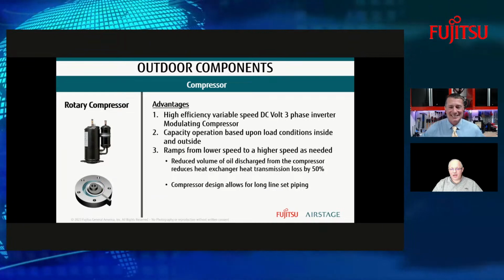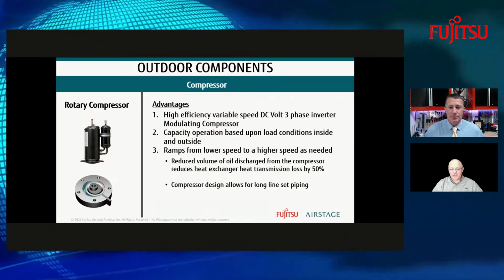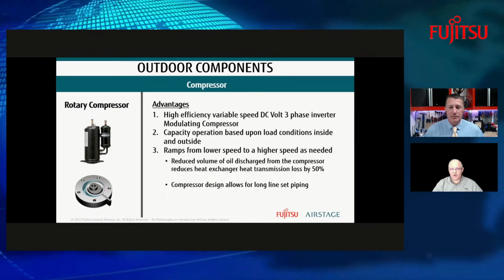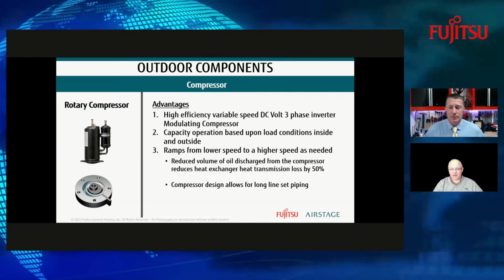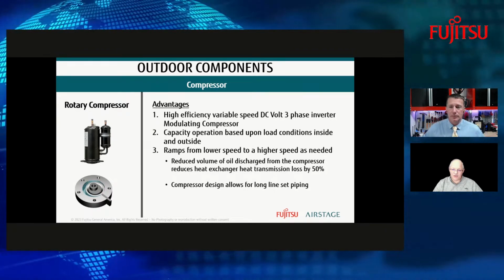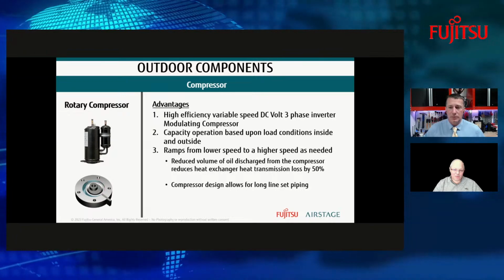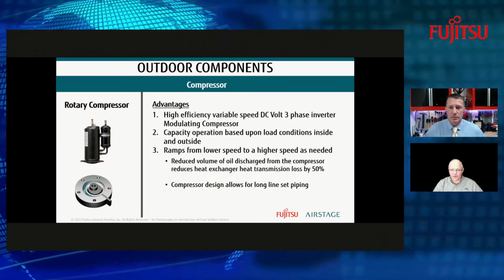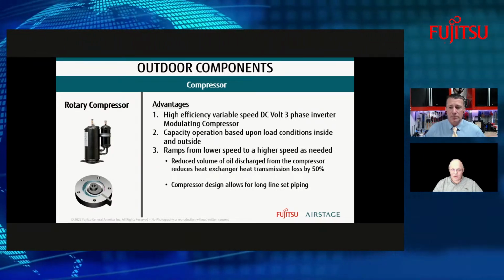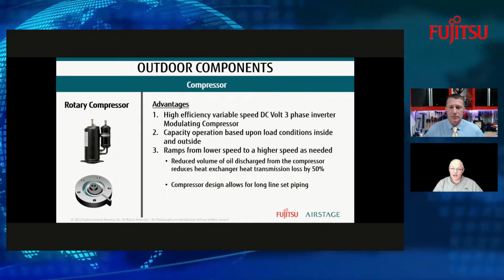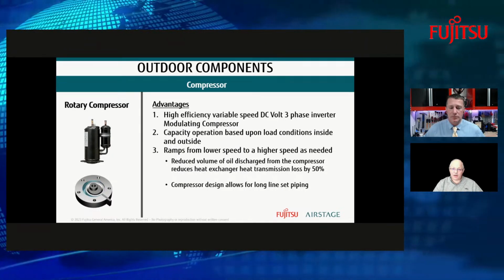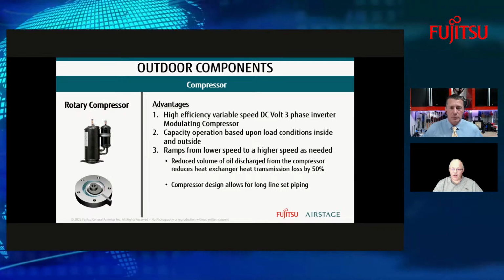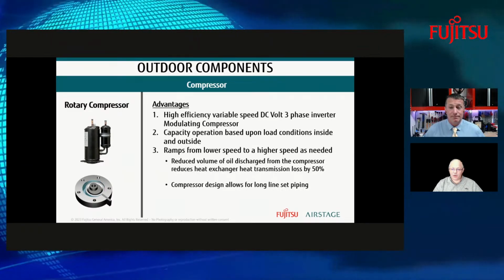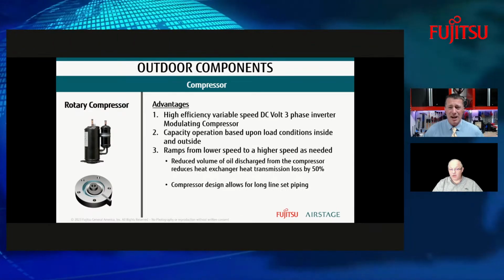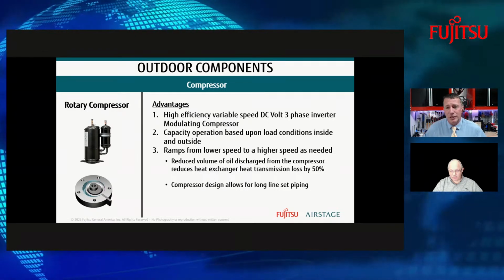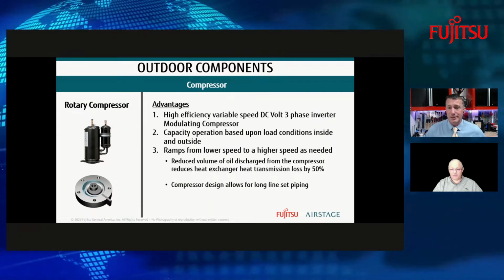And it's interesting how, because of its design, especially when you're looking at getting oil return back to the system. Right. Very important. Yeah, there's a lot of guys say, well, how can you pipe something out 164 feet or 230 feet? I can't do that with a traditional system. And it has to do with the speed that the rotary compressor can run and ramp up to get the oil back to the system. So yeah, a lot higher RPMs than people are traditionally used to, especially with recips and scrolls.